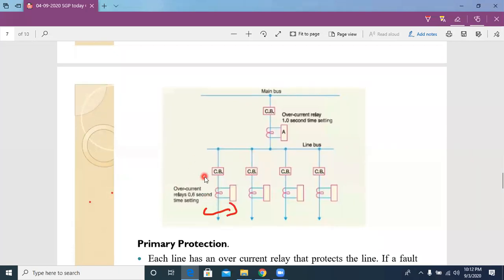So here, for protection purposes, we place a relay. Here the fault has happened, and the fault is detected by the relay. When it detects the fault, it sends a signal to the circuit breaker, and the circuit breaker contacts open. When the circuit breaker contacts are open, this particular section is isolated from the remaining one. This is the successful case.